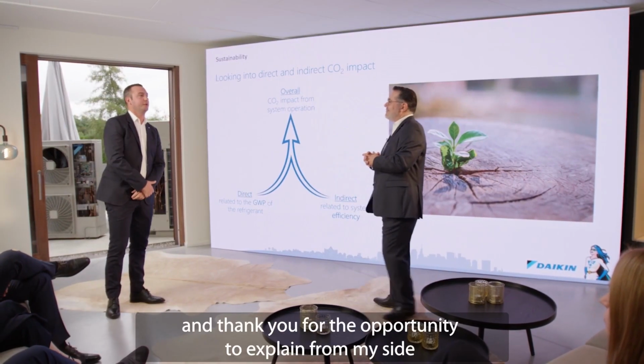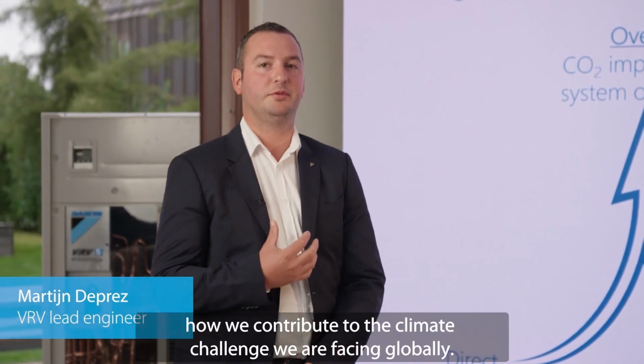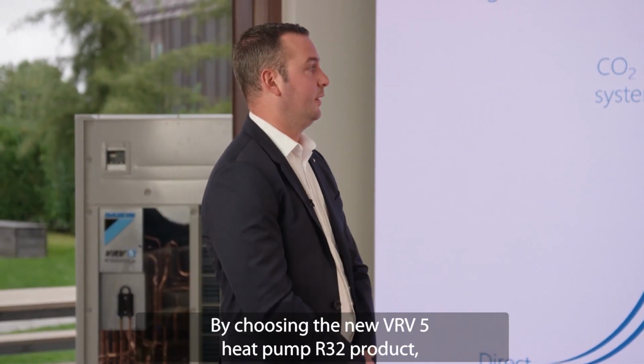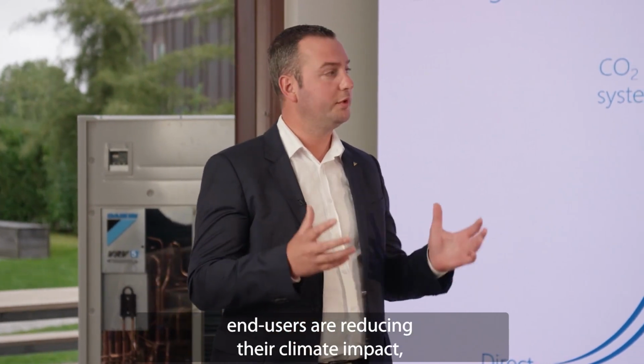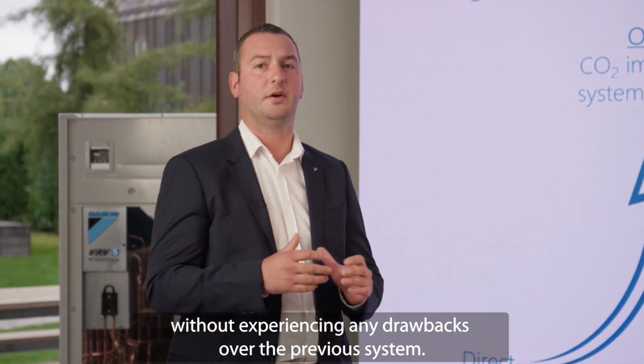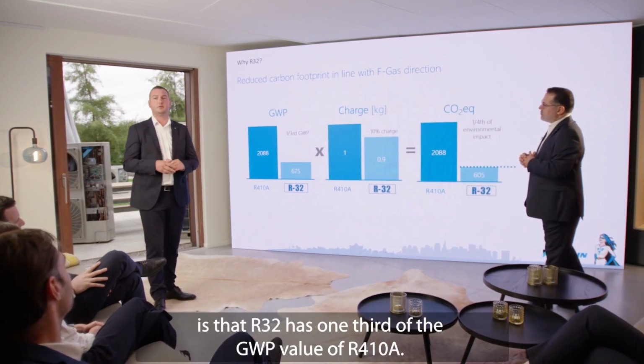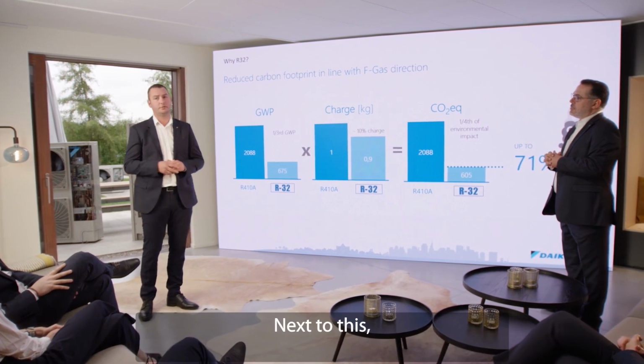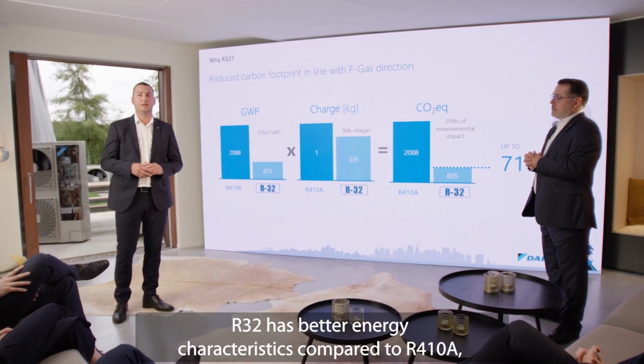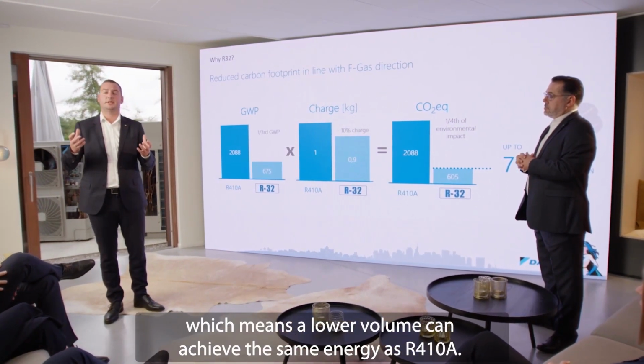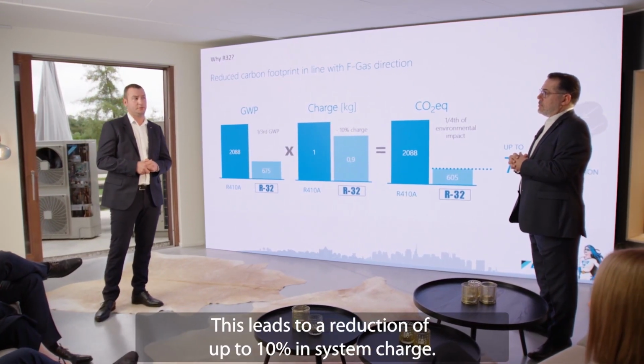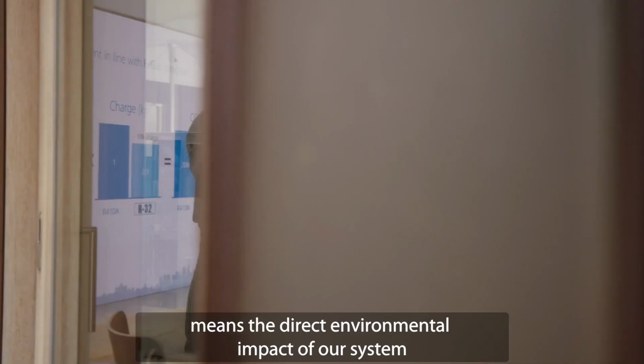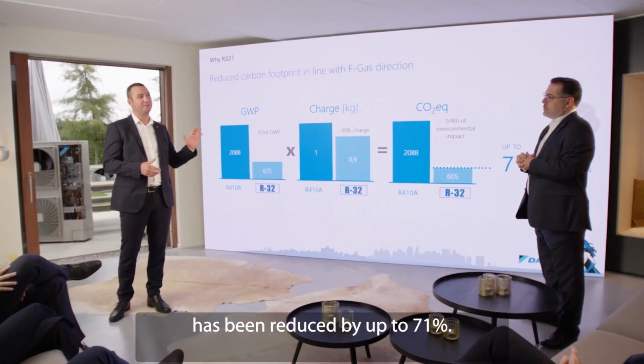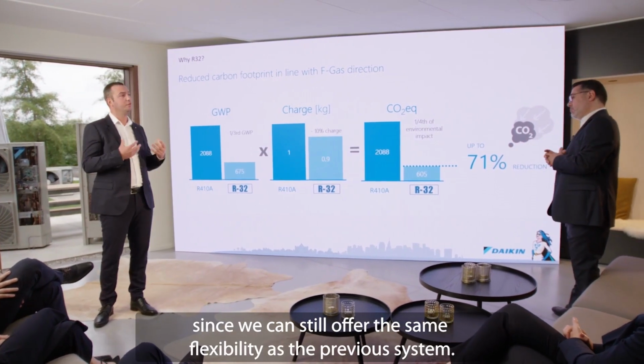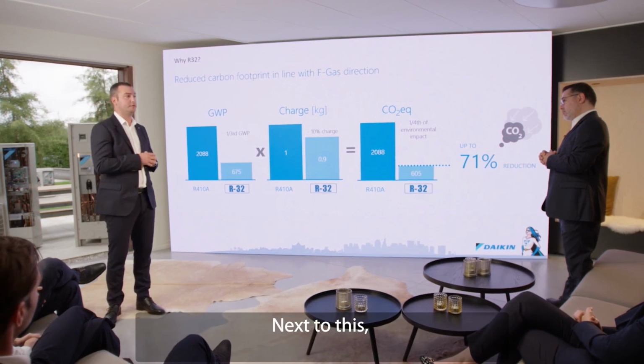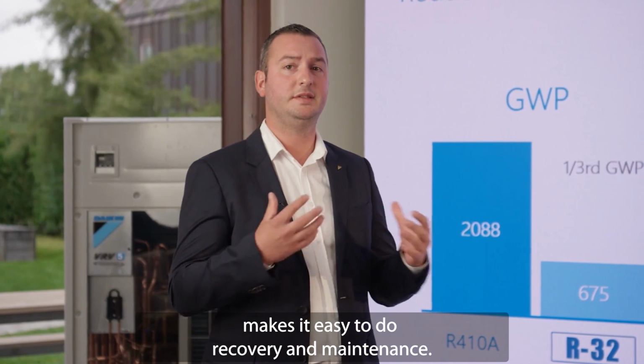Thank you, George, for the short introduction, and thank you for the opportunity to explain from my side how we contribute to the important climate challenge that we are facing today globally. By choosing for the new VRV5 heat pump R32 product, end users are contributing to reduce their climate impact without experiencing any drawback on the previous system. One of the main reasons is R32 has 1/3 of the GWP value compared to R410A. Next to this, R32 has better energy characteristics compared to R410A, meaning with a lower volume you can achieve the same energy amount as R410A, which leads to a reduction up to 10% system charge. This, together with a lower GWP value, means the direct impact of our system to the environment has been reduced up to 71%. This is a huge achievement, George, considering we can still offer the same flexibility as the previous system. And next to this, R32, being a single component refrigerant, makes it easy to do recovery and to do maintenance.